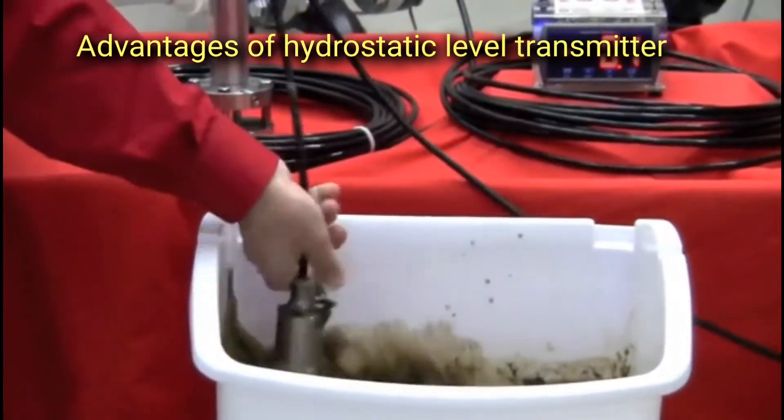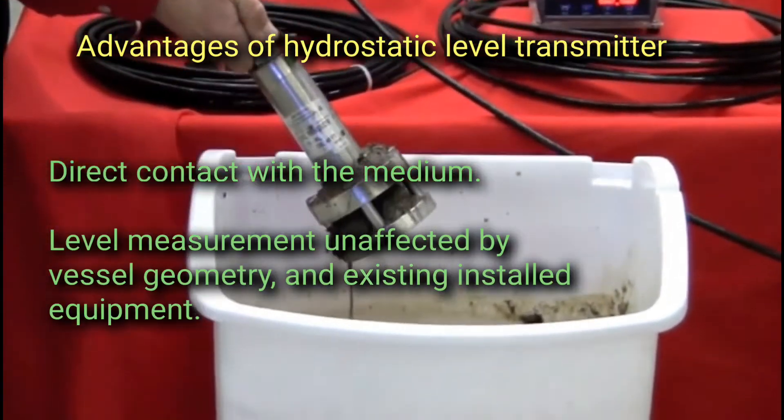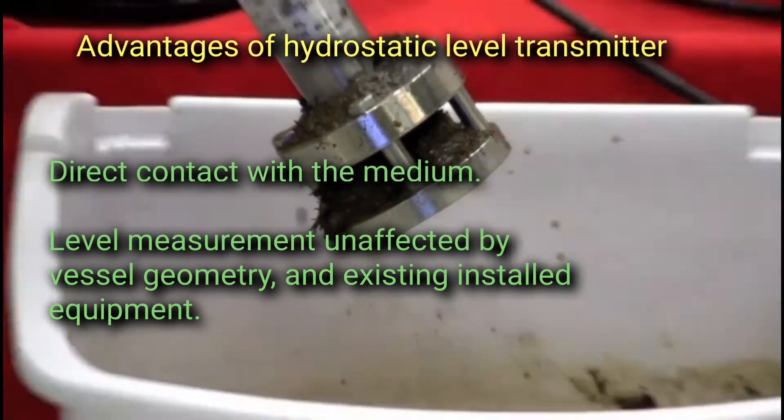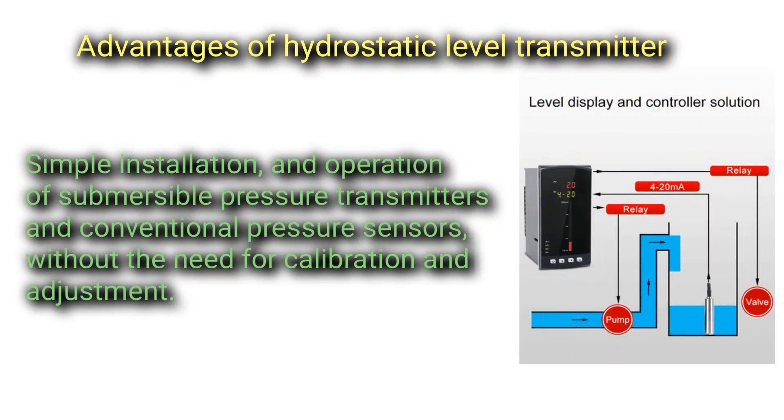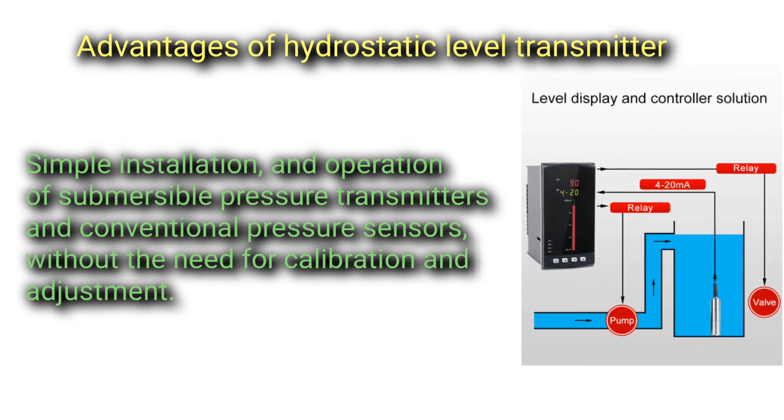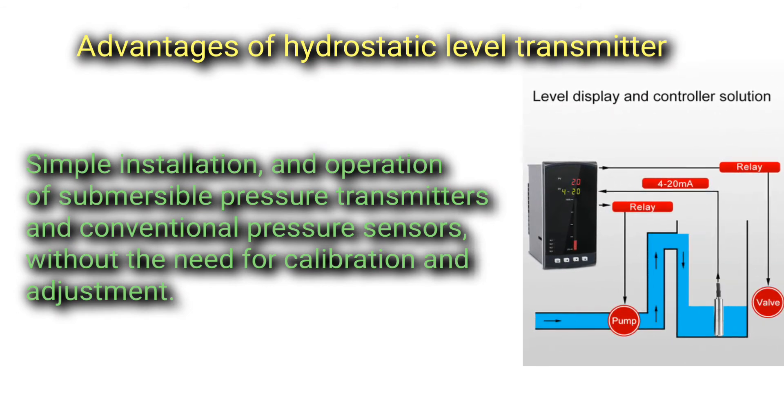Advantages of hydrostatic level transmitter: Direct contact with the medium. Level measurements unaffected by vessel geometry and existing installed equipment. Simple installation and operation of submersible pressure transmitters and conventional pressure sensors without need for calibration and adjustment.